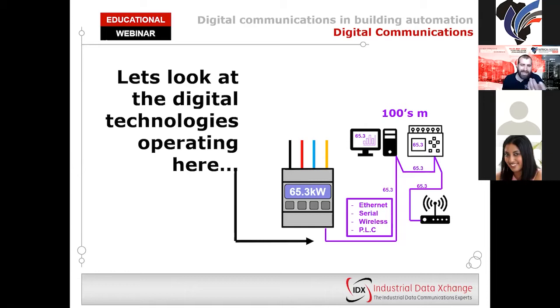Within a LAN environment, we can also distinguish isolated versus integrated networks. An isolated network typically involves only a few devices linked together that directly require one another to perform a task. Isolated networks aren't linked to a larger building-based network—they might span only a single room, for example. An example might be an occupancy sensor linked to a light relay, which is linked to a room-specific HVAC controller, for heating, ventilation, and cooling.